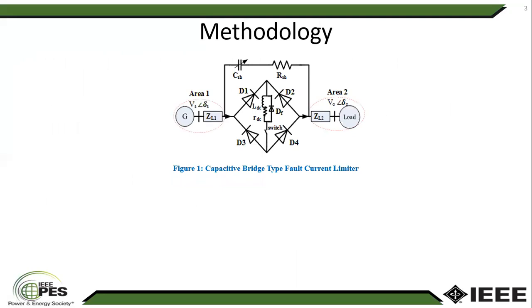This is the structure of the capacitive bridge type fault current limiter. There are two particular parts. The first part is the bridge part which conducts during normal operation of the power system. There is a switch which is a power electronic based switch and there is a shunt path which has a shunt resistance and variable capacitance. They conduct or limit the flow of high current when there is any disturbance or fault into the power grid.